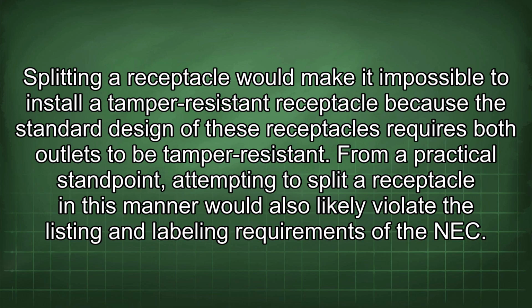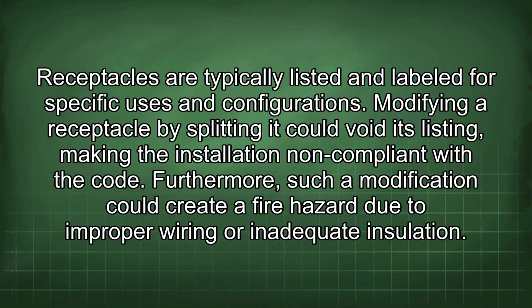From a practical standpoint, attempting to split a receptacle in this manner would also likely violate the listing and labeling requirements of the NEC. Receptacles are typically listed and labeled for specific uses and configurations. Modifying a receptacle by splitting it could void its listing, making the installation non-compliant with the code. Furthermore, such a modification could create a fire hazard due to improper wiring or inadequate insulation.